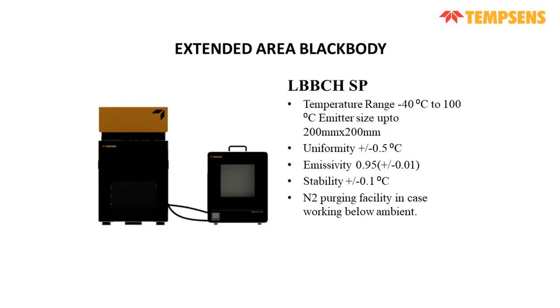So when we are going below ambient or below 0° or 5°, there are chances that ice will get deposited on the emitter. So for that, a nitrogen purging facility is also given, and it can also be incorporated with an anti-condensation chamber, which will be attached on the front of the emitter.